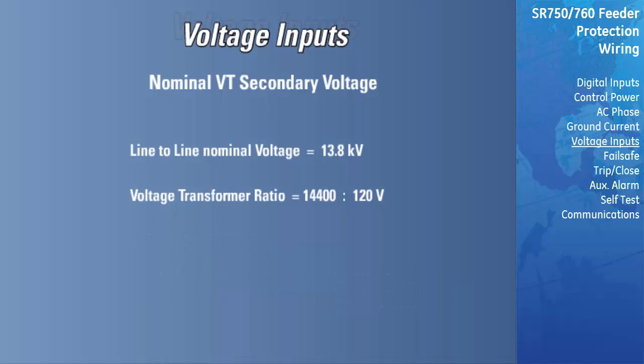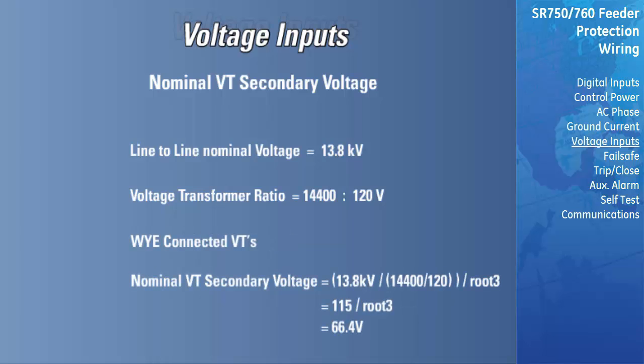With a Y configuration, you must take the line-to-line nominal voltage calculated for a delta configuration and divide it by √3 in order to get the line-to-neutral voltages that the relay will be seeing. Considering the previous example, the 115-volt line-to-line secondary voltage will be divided by √3 for a line-to-neutral secondary voltage of 66.4 volts. The line voltage input is used for the synchro-check function of the relay.